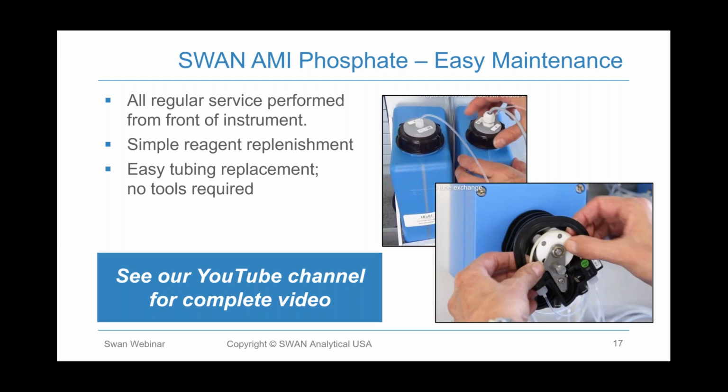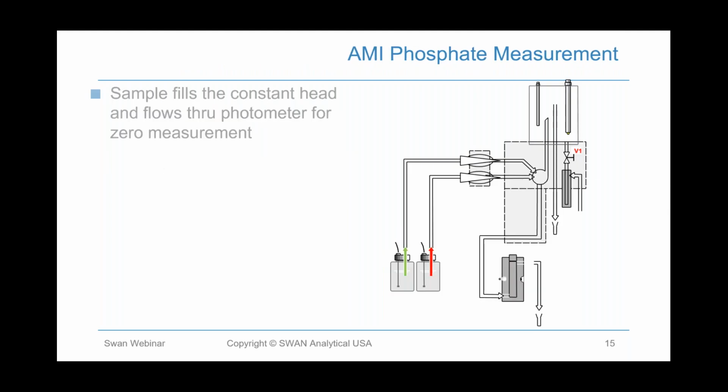So there's no tubing kits, there's no pinch plates, there's no air pump to maintain. That is it, and it is a real, I don't want to say joy to work on this instrument, but it's very nice knowing that that is the only wearable part on the instrument. And then we've got a YouTube channel that actually shows maintaining that, and maybe we can send the link out to the attendees here. So this is a little bit about the fluidics of the analyzer.